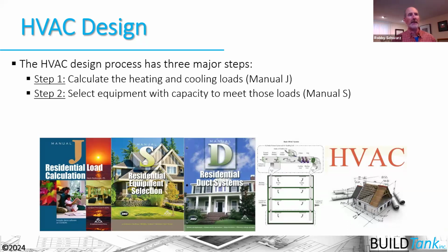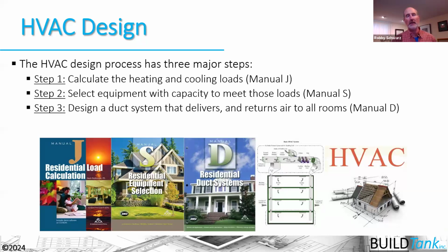Then our next step is to select equipment that has the capacity to meet the loads that are determined by the Manual J calculation. So that's all wrapped up in the Manual S calculation there. And then lastly, when we're talking about duct systems, we need to design the duct system that ultimately delivers the heat via air to different rooms around the house.